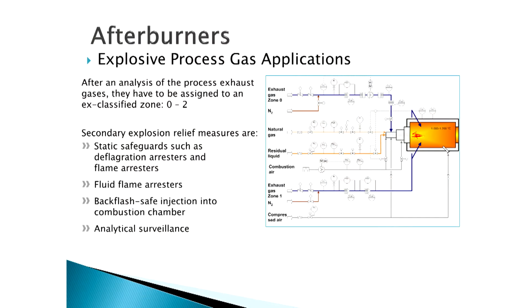A lot of times we deal with explosive gases in these applications. So in terms of the different trains that we have to assemble ahead of the system and the different burner arrangements, there are a lot of important explosive classifications that we have to meet. There are a lot of safeguards, such as deflagration arresters and flame arresters and things of that nature. Normally we see these types of devices deployed in industries where you would expect very high chemical concentrations: petrochemical, the chemical industry, pharmaceutical in many cases, and so forth. So that's just loosely what an afterburner looks like.